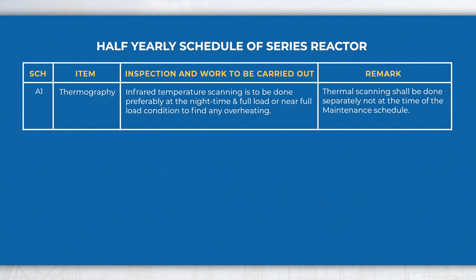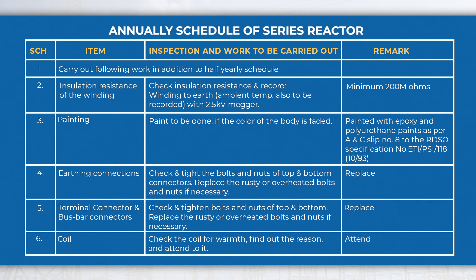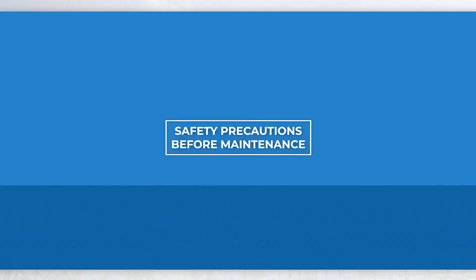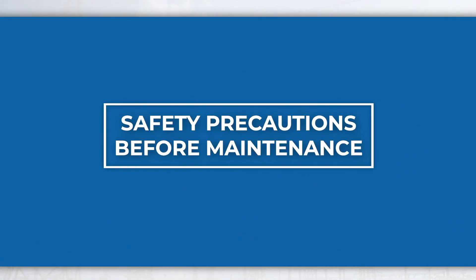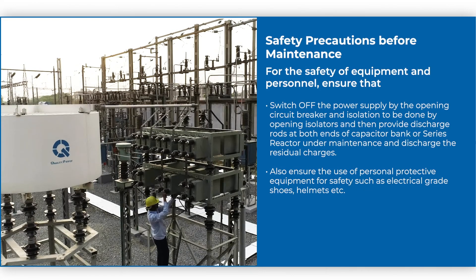In the half-yearly schedule of the series reactor, perform activities like thermography, etc., in addition to monthly schedule activities. In the annual schedule of the series reactor, perform activities like insulation resistance testing of winding, tightness of earthing connections and terminal connections, etc., in addition to half-yearly and monthly schedule activities.